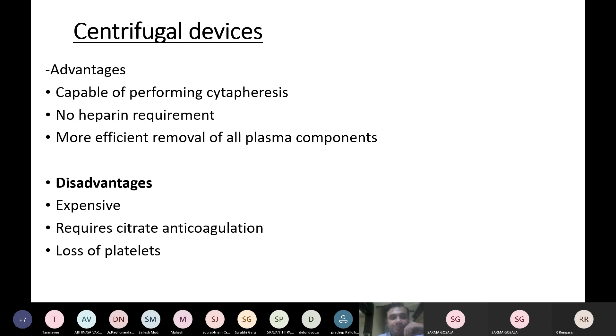What about the centrifugal device? It has a good advantage of performing cytopheresis. There is no need for heparin, and it is more efficient for removing all the plasma components. Well, it has its own disadvantages. It is expensive. The machine itself costs around 15 to 18 lakhs, and per session of plasma exchange it costs around 18 to 22,000. So the whole 5 sessions of plasma exchange with this centrifugal device come to around 1.2 to 1.5 lakhs. And it also requires citrate anticoagulation and causes loss of platelets.